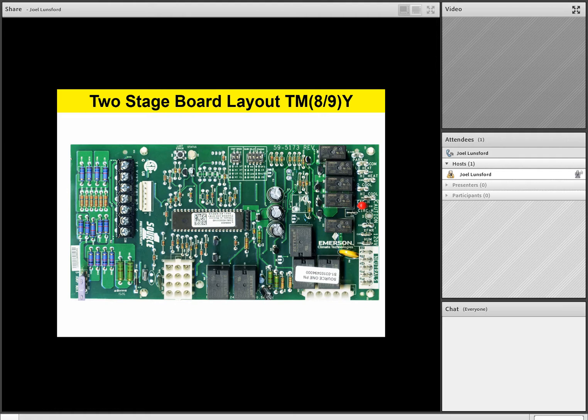So if you'll take your handout or your workbook, and please follow along as we go across the picture and we talk about all the inputs and the outputs on the two-stage TM9Y, TM8Y board. So starting in the upper left-hand portion of the board, let's talk about our low voltage wiring like we did before. So going up to the thermostat, Y1 will be our first stage cooling call. Y2 will be our second stage cooling call. W1 will be our first stage heating call.